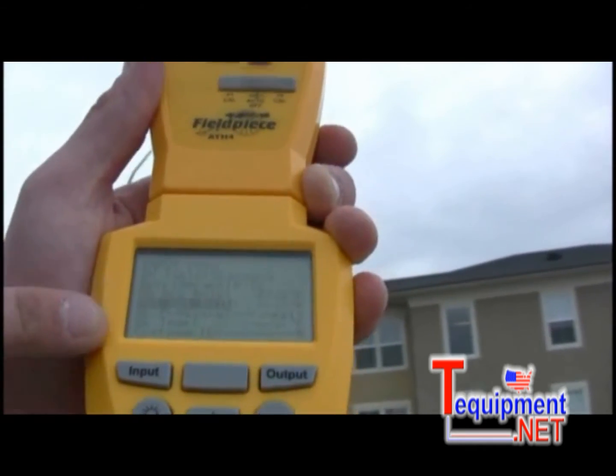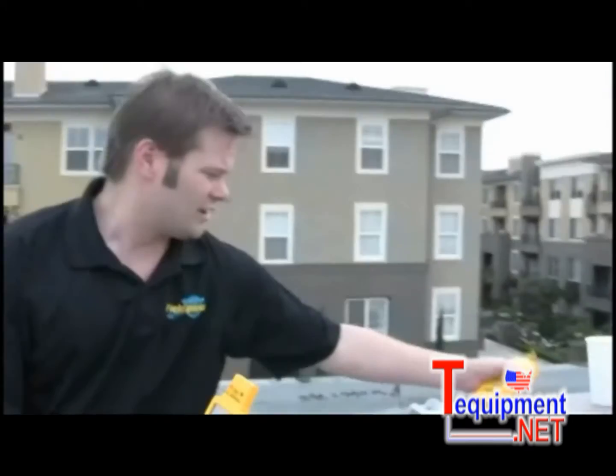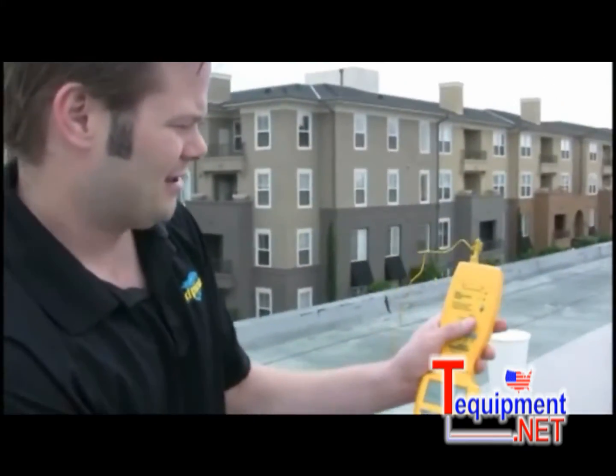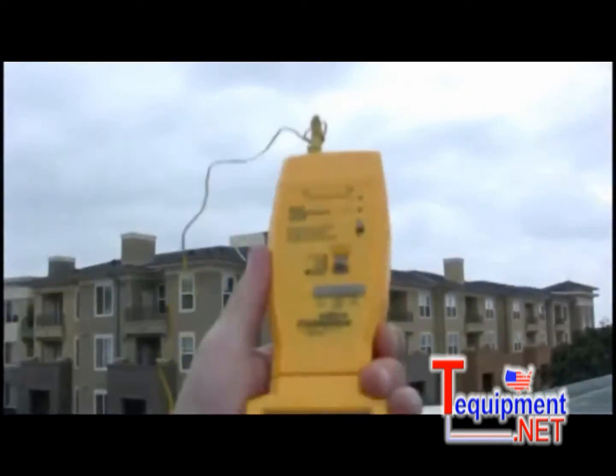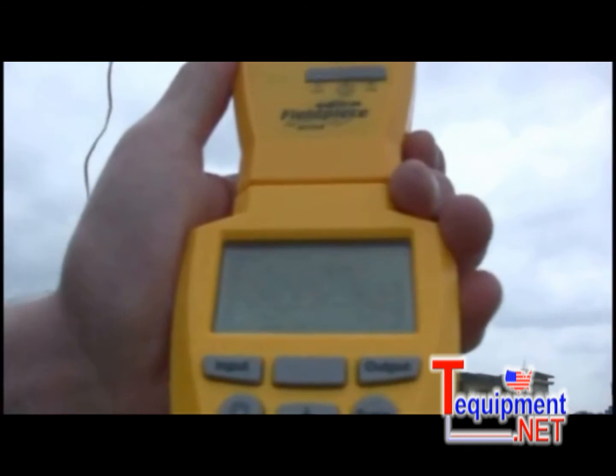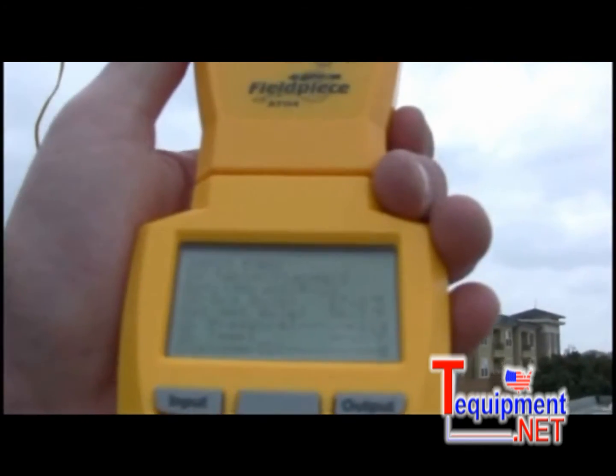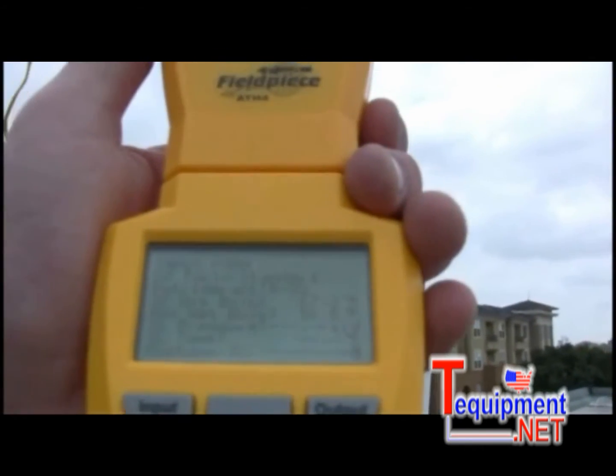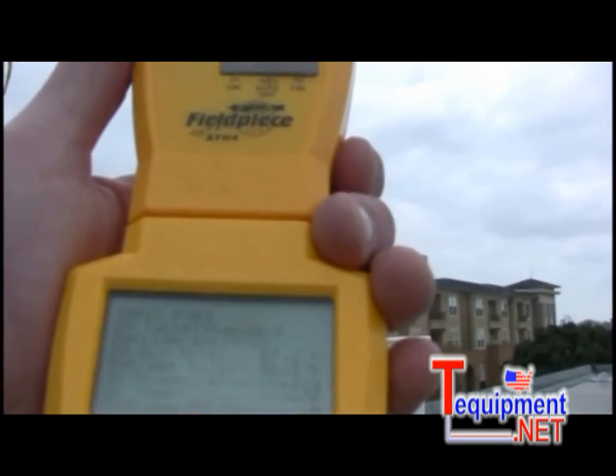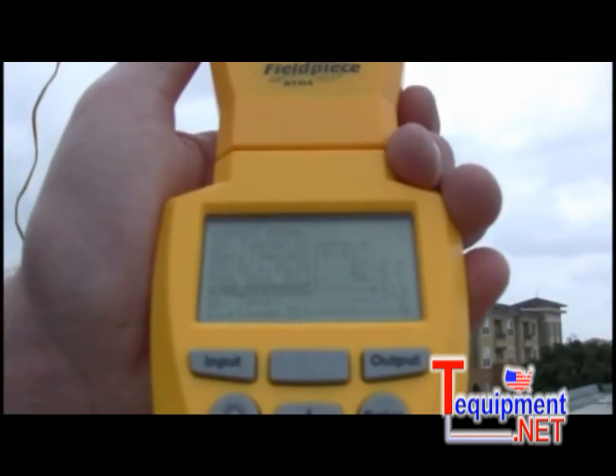The next step is the return wet bulb. I have my wet bulb thermocouple hooked up over here. So all I have to do is attach this head, turn it on, and press enter to start taking the measurement, and you can see that I have a 56 degree wet bulb. So I'm going to make sure that's stable. Looks like it's pretty stable, and I'll press enter to lock that in.